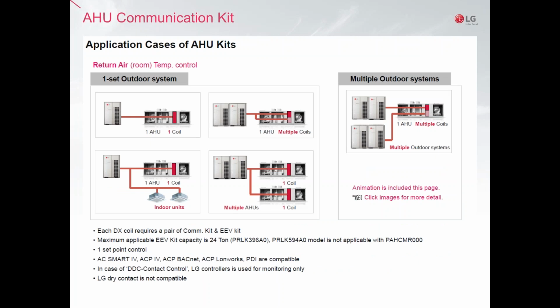Now, these are some configuration examples of systems installed with the return air controller. The idea of this slide is to show you some ways to connect the systems and how they can be used. In the top left side, you will see a very simple and straightforward design, one-to-one. So you have one outdoor unit connected directly to one single coil in a typical air handling unit. This is a very common design where the maximum capacity of the system is limited by the maximum capacity available in a single module, that in Multi V5 LG air-cooled is 20 ton, which is the best in the market.